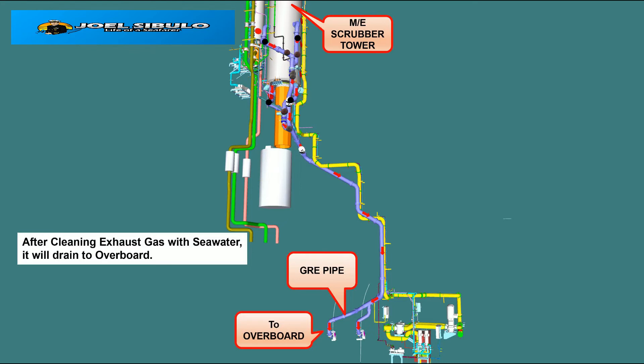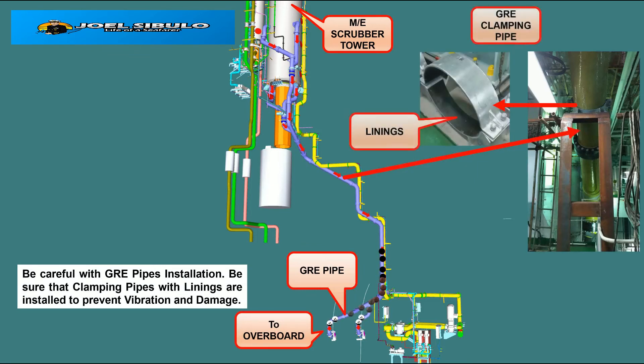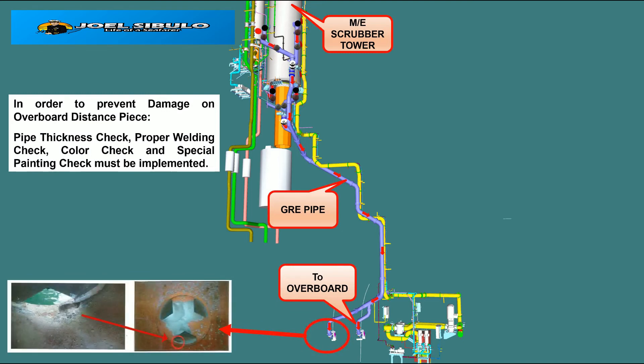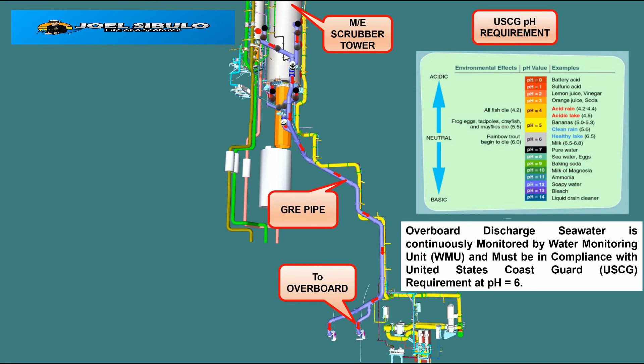After cleaning exhaust gas with seawater, it will drain to overboard. Be careful with drain pipe installation; be sure that clamping pipes with lining are installed to prevent vibration and damage. In order to prevent damage at the overboard, check proper welding, color code, and special painting. Overboard discharge seawater is continuously monitored by the Water Monitoring Unit, WMU, and must be in compliance with United States Coast Guard, USCG, requirements at pH equals 6.